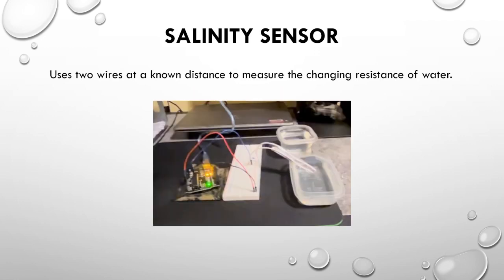The salinity sensor uses 2 wires at a known distance to measure the changing resistance of water. Water, like any fluid, is measured in ohm times unit distance. As water gets saltier or has more minerals, the conductance goes up — it conducts electricity better — meaning the resistance gets lower, which can be measured digitally.